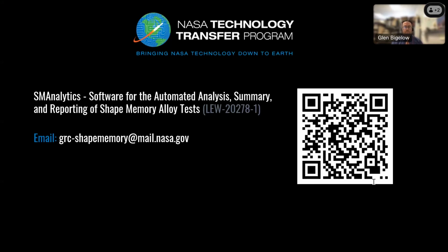Okay, very good. Thank you. Okay, next question. Thank you for this wonderful work. And this person has a question about DSC data evaluation. Sometimes we can see 2 peaks because of the different transforming phases, such as R phase. How does this software handle this type of data? Can it report 2 different TT for a single DSC curve?